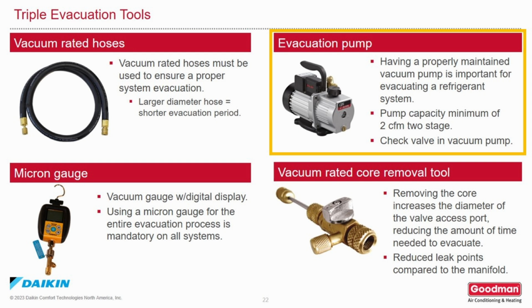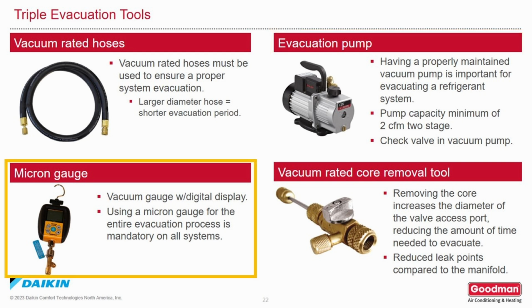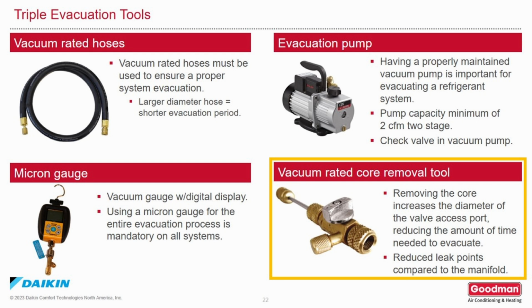Vacuum pump oil must be changed frequently, not only when the vacuum pump tips over in the back of the truck. A micron vacuum gauge is an absolute necessity for the entire evacuation process. Without a vacuum gauge, there's no way of knowing when you have a proper vacuum. Manifold gauge sets will not show you that information. And lastly, use a vacuum-rated Schrader core removal tool. Removing the core increases the diameter of the valve so it reduces the time of the evacuation. There are reduced leak points compared to using a manifold gauge set.